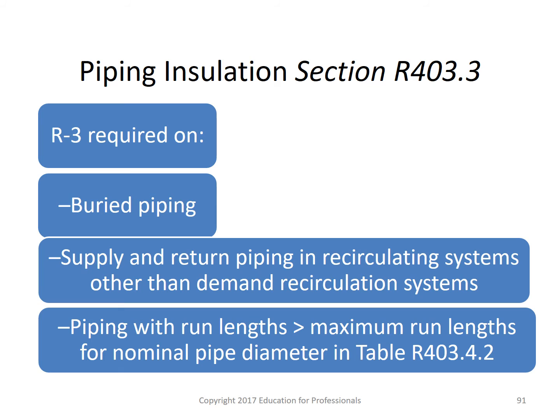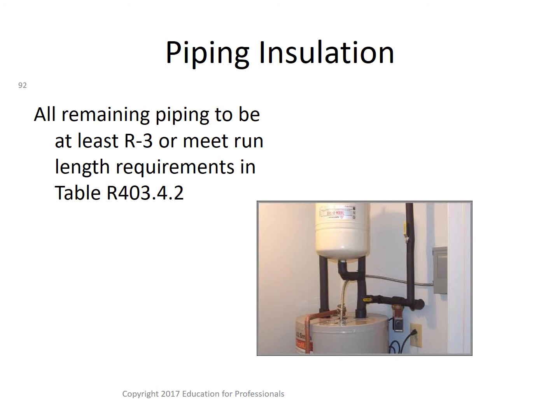R3 is also required on buried piping, supply and return piping, and piping with run lengths greater than the maximum run lengths for nominal pipe diameter, as described in Table R403.4.2. And all remaining piping to be at least R3 or meet run length requirements in the aforementioned table.